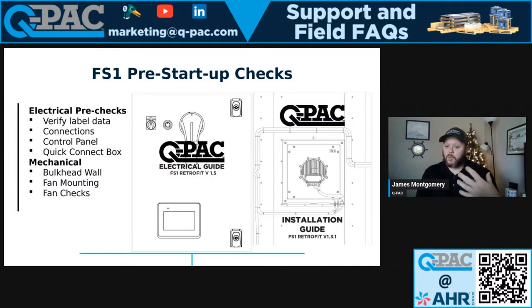Also, there's an inlet cone or a volute on the inlet side of the fan. Oftentimes, because that moves independently of the fan itself, it is tightened down with 10 millimeter bolts, but oftentimes that can get jarred a little bit and it will come into contact with the blade. There's a very small tolerance for that blade, and it's not a measured gap, but if it comes into contact with that blade, it's going to deteriorate. A lot of our blades are composite, some are not, but either way, if that volute is coming into contact, you can loosen those bolts and realign that volute or that inlet cone to make sure that it's not making contact. And then again, listen for any kind of obstruction. Before you spin these things full on, we want to make sure there's no debris in it, no user's guides left in it, no screwdriver, no nuts or bolts, any of those common things. In the military, we refer to that as FOD, foreign object debris. You want to make sure that that's not in there.